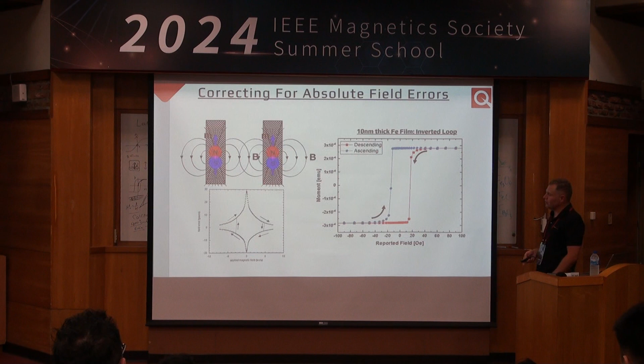I still get one of these emails once a month from somebody. They're like, what's going on? Is this new physics? No, this is not new physics. This is an instrument artifact that you can totally correct, and I'll show you how we correct this. It's a natural consequence of this remnant magnetic field. Now in our PPMS product line, let's say you pony up for a 16 Tesla system. The bigger the magnet is, the more room there is for the stray currents to hide. We can get remnant fields of up to a couple hundred Oersted or so. It's very sizable. And again, we suffer from the same problem, except it would be a magnet problem here.